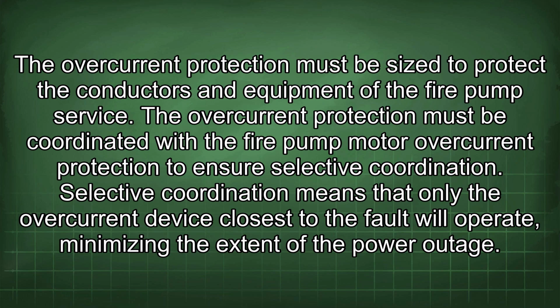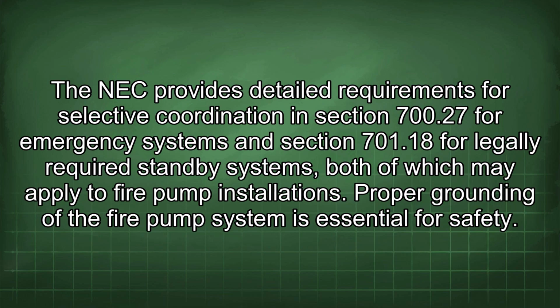The overcurrent protection must be coordinated with the fire pump motor overcurrent protection to ensure selective coordination. Selective coordination means that only the overcurrent device closest to the fault will operate, minimizing the extent of the power outage. The NEC provides detailed requirements for selective coordination in Section 700.27 for emergency systems and Section 701.18 for legally required standby systems, both of which may apply to fire pump installations.